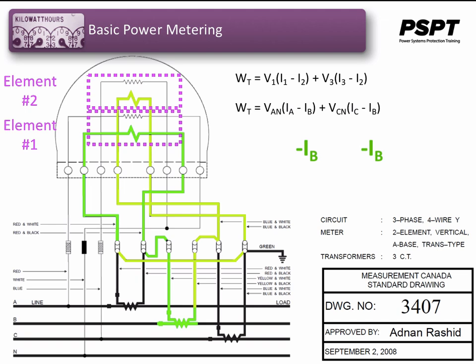Now IB, or the B phase current, goes through both elements, and it leaves the CT using, I'm associating it with a dark green, and you can see it goes up and through element number 1 backwards, which means it's being subtracted, or minus B, through element number 1. It comes back down, but doesn't return directly to the CT, but goes up and backwards through element number 2, which gives it a minus B for element number 2, which is shown in the light green here. After it goes through element number 2 backwards, it returns back to the CT and continues the circuit flow.